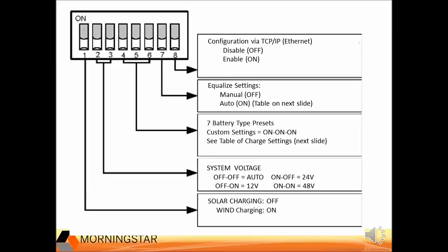If you don't turn anything on, it defaults to the lowest voltage and auto-detects the nominal battery voltage of 12, 24, or 48 volts. This makes it safer if someone decides to install it without setting the DIP switches — in a sense it is a plug-and-play device even without any DIP switch adjustments. If someone installs a 12, 24, or 48 volt nominal lead acid battery system and comes back later to make adjustments, that should be no problem as long as the remote temperature sensor is used, especially in warm climates. The proper preset or custom setting needs to be used for the final installation for the long-term health of the battery, but those low voltage settings are not going to be harmful if you install it without changing the DIP switches.